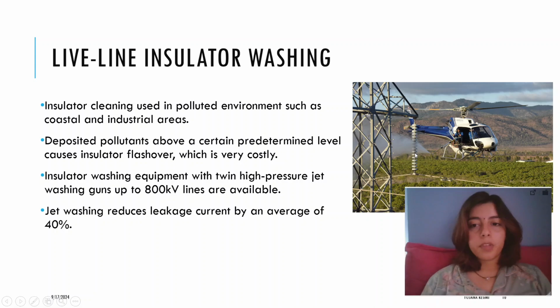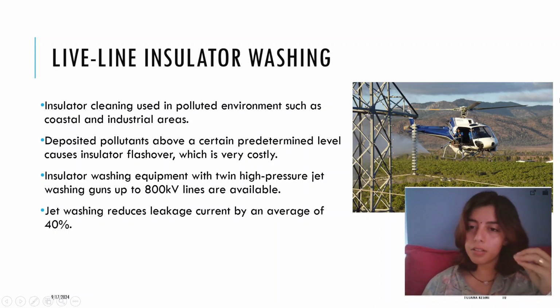Regarding insulator washing, if you are in a coastal area, the air surrounding you will be full of salt. Salt deposits will be on the insulators near coastal areas such as the sea or oceans. The air will have some concentration of salt, and over time it gets deposited on the surface. In industrial areas, there will be dust, smoke, and various other pollutants in the environment, and they will settle on these insulators. Due to these pollutants, there can be an insulator flashover, which is very costly. With these pollutants, the electricity is able to pass through them, and the flashover will damage the insulator, and we have to replace it.